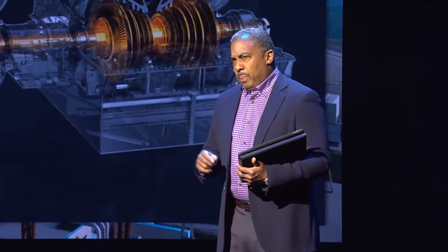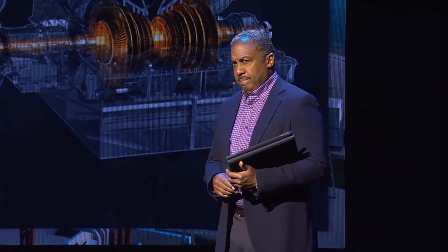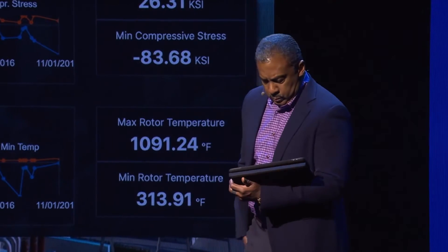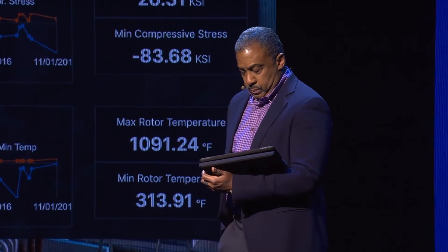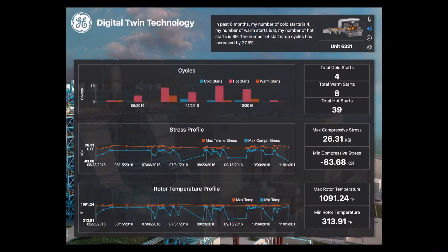What's your operating profile? In the past six months, my number of cold starts is four, my number of warm starts is eight, my number of hot starts is 39. The number of start-stop cycles has increased by 27.5%.